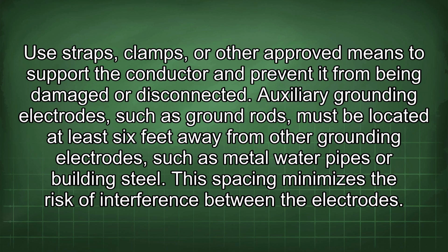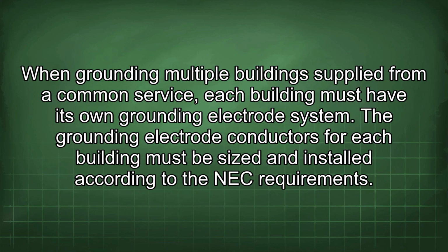Auxiliary grounding electrodes, such as ground rods, must be located at least 6 feet away from other grounding electrodes, such as metal water pipes or building steel. This spacing minimizes the risk of interference between the electrodes. When grounding multiple buildings supplied from a common service, each building must have its own grounding electrode system. The grounding electrode conductors for each building must be sized and installed according to the NEC requirements.